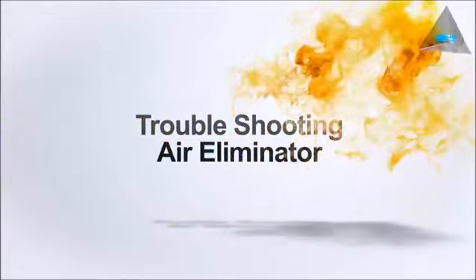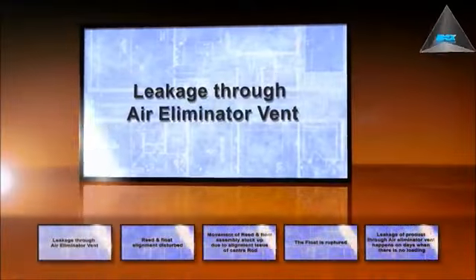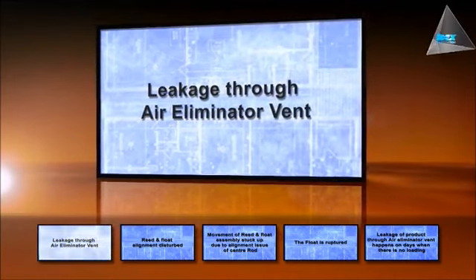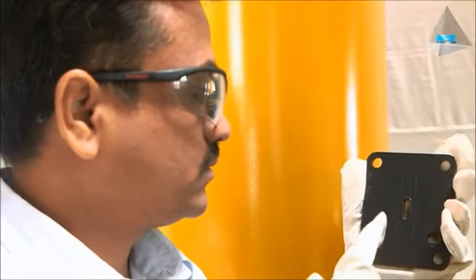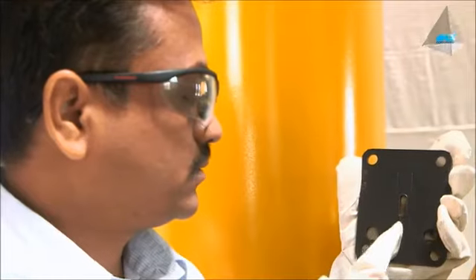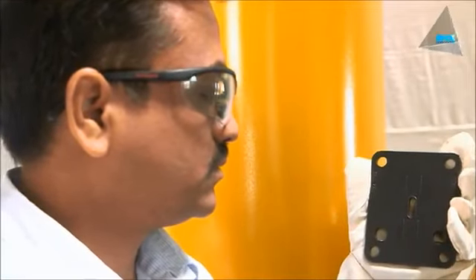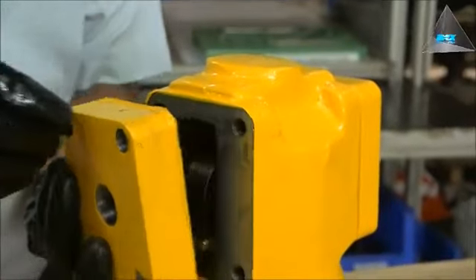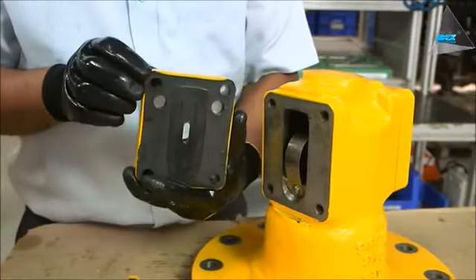Troubleshooting air eliminator. Leakage through the air eliminator vent. Possible cause: foreign particles deposited on the reed and valve plate near the vent due to atmospheric dust or with product. Solution: open the assembly, inspect and clean the surface of dirt and reassemble.